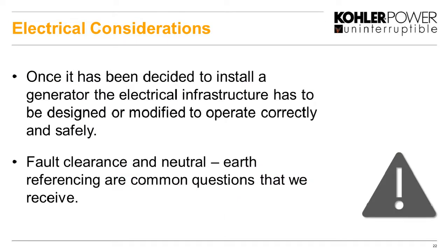So, once we've decided we're going to put an installation of a generator in, we have to make sure that we do it properly. So, with the electrical considerations, that might depend if it's going to go in as a modification to the infrastructure, or it's going to be designed in from the beginning. Both things have to be considered. And some of the things that we get asked about are fault clearance and neutral referencing when we're looking at generators as well.